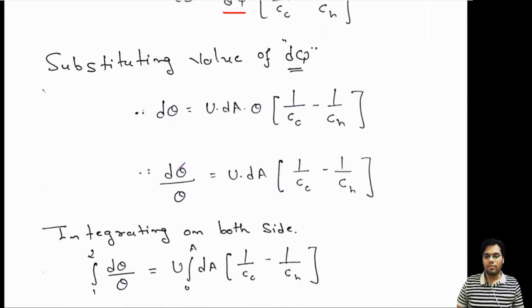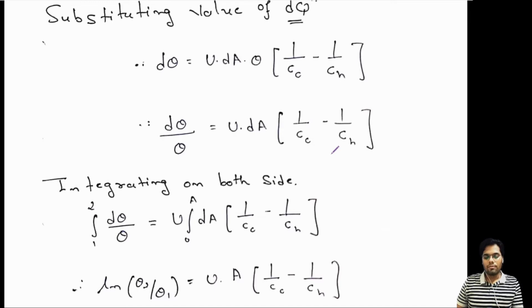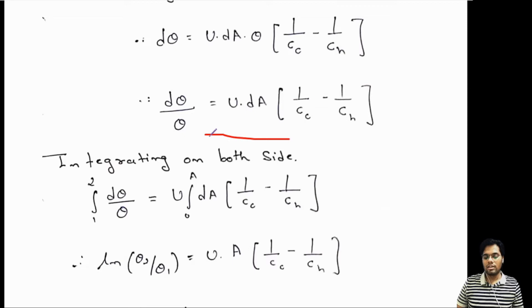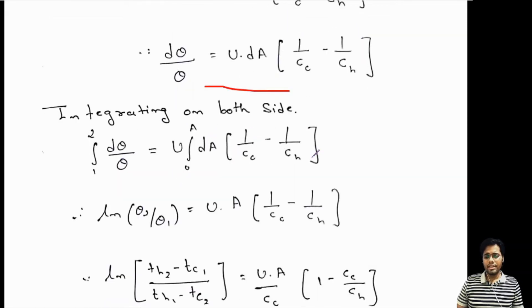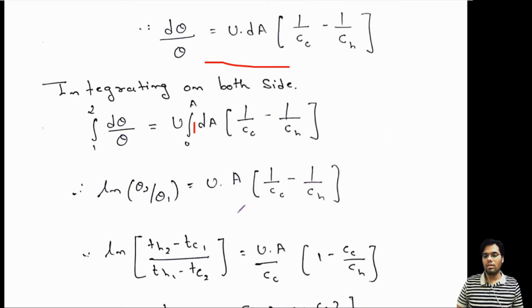To get the equation for the whole heat exchanger, we integrate. For theta, the limits are the inlet and outlet conditions: subscript 1 for inlet and 2 for outlet. For area, the limits are 0 to A. Integrating, 1/theta integrates to ln(theta), giving ln(theta2/theta1) on the left side, and UA·(1/CC - 1/CH) on the right side.